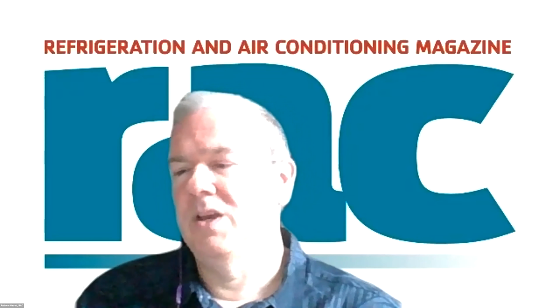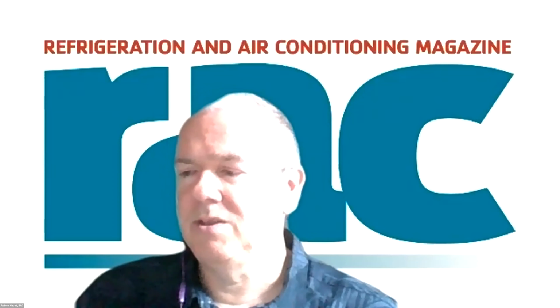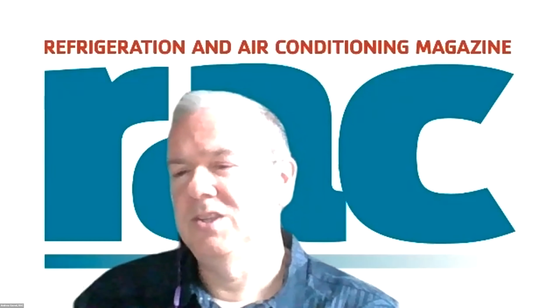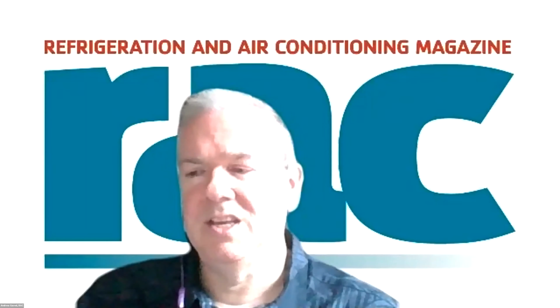So first of all, a couple of little public information statements. Thanks to the audience for sending them in. The standard to follow for strength and pressure testing is EN 378. This is mostly if you're dealing with contractors, and the contractors are looking in. Lots of supporting information for you. Also, the IOR has a series of safety guidance notes, safety codes of practice for flammable and lower toxicity refrigerants: A2L, A2, and A3. So contact the IOR for those.